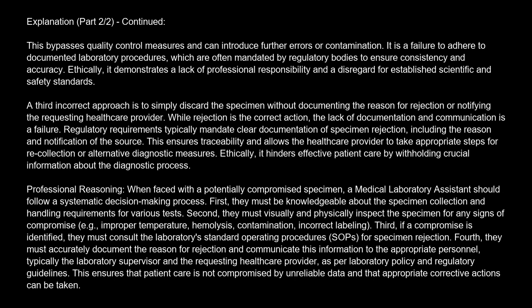Professional reasoning. When faced with a potentially compromised specimen, a medical laboratory assistant should follow a systematic decision-making process. First, they must be knowledgeable about the specimen collection and handling requirements for various tests. Second, they must visually and physically inspect the specimen for any signs of compromise, e.g., improper temperature, hemolysis, contamination, incorrect labeling. Third, if a compromise is identified, they must consult the laboratory's standard operating procedures, SOP, for specimen rejection.